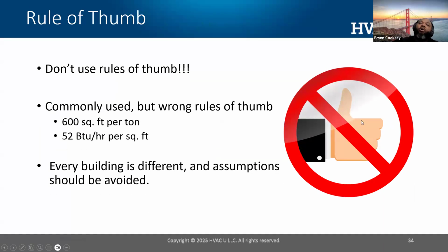All right. So as you're running your programs, it's always important to remember there are no rules of thumb. There were tribal knowledge rules that were passed on from generation to generation in the skilled trades, and they are all inaccurate. Whenever you want to evaluate a building shell to install a heat pump, you should always, always, always perform a Manual J calculation. All right, every building is different, and assumptions should be avoided. Let's take a look at an example.